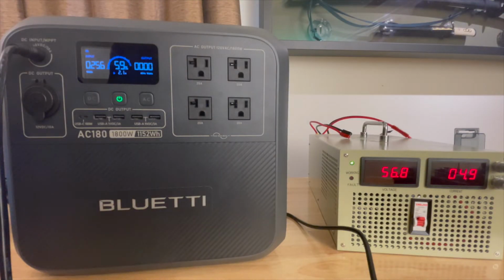If you have panels pretty close to the edge and you get an event like a cloud edge type event, where you get more light than expected and your panels put out too much voltage for a minute or so, the device will automatically reset the error. Now if you go way over the rated voltage, and I don't know exactly where the edge of the safe area is, but if you go way over it, it is possible to damage this by overvolting it, so I wouldn't recommend pushing the hard end of that envelope. But it is nice that it does reset.